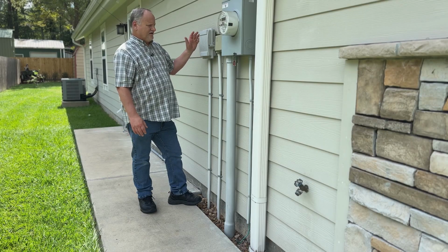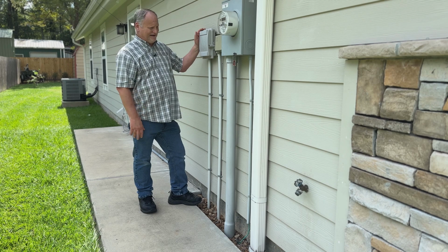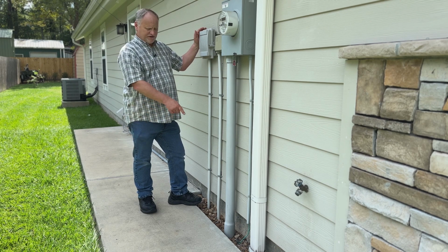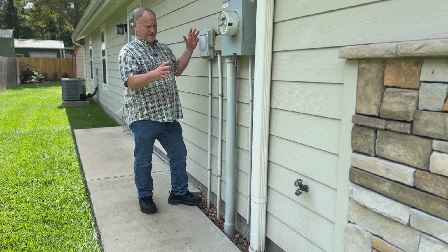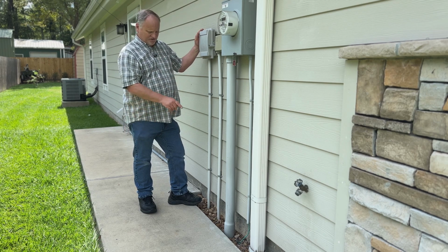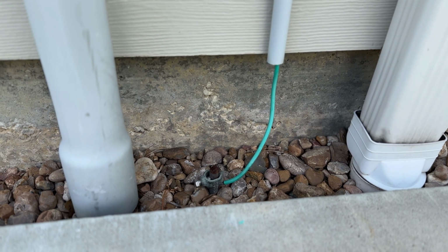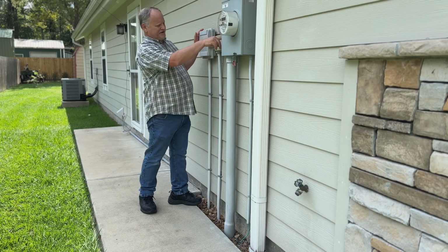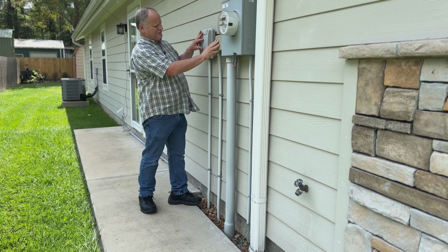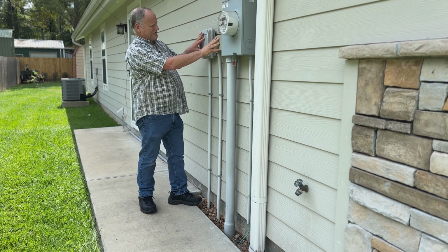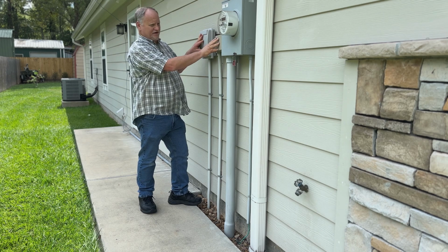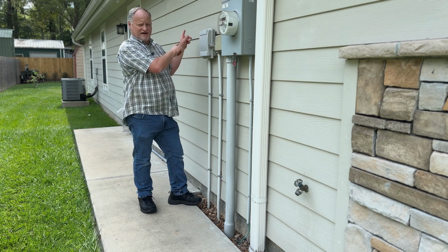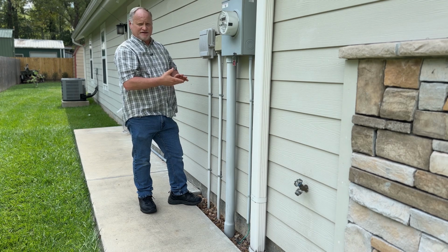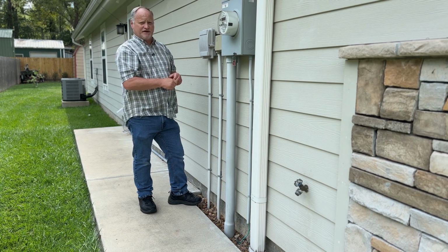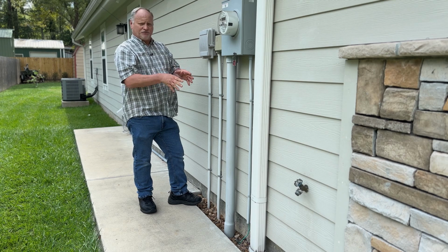First, let's talk about grounding. All right, it all starts with a common ground point in a house or a building, wherever it is, usually located by the power meter and the utilities that come into the place. A ground rod right down there feeding the panel, which is going inside. It also back feeds into these two here, which is telephone, your internet, and cable TV internet. It also feeds it here as well. And all of the common grounds in the house, your refrigerator, your stove, everything that has a ground to it is tying back to this location. So this is your central ground right here.